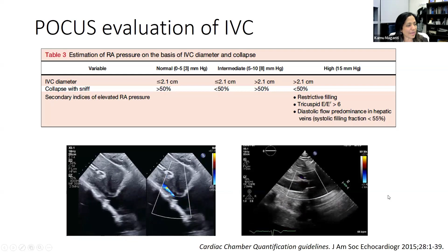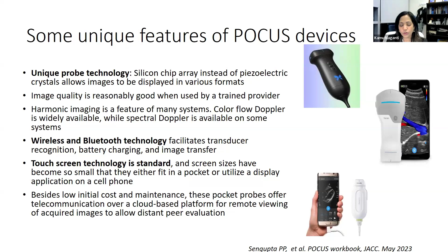And some of the unique features of POCUS devices are things that we need to take into consideration. The probe technology is extremely unique. It's got a silicon chip array instead of the piezoelectric crystals, so the chances of destruction of the probe are a lot less. Image quality is reasonably good if it is a trained provider. Harmonic imaging is available. Wireless and Bluetooth technology allow transducer recognition, battery charging, and image transfer, and touchscreen technology is standard. In addition, cloud-based interpretation is possible for remote viewing.